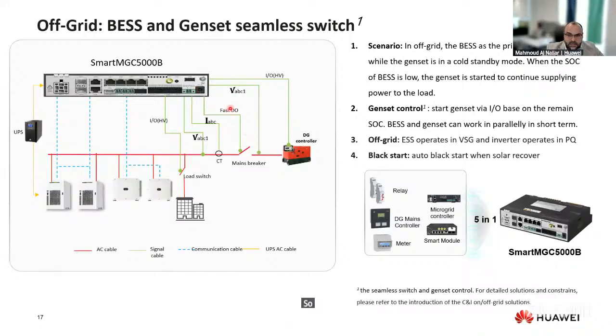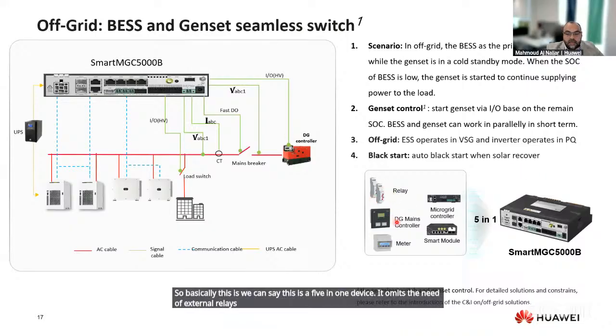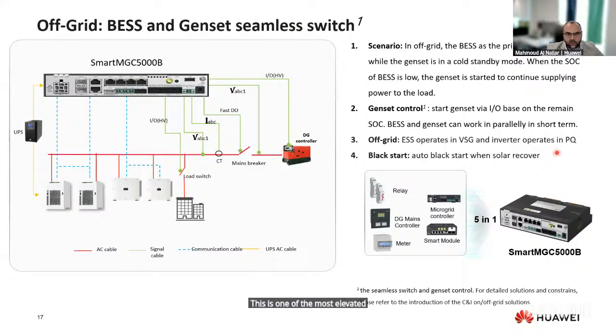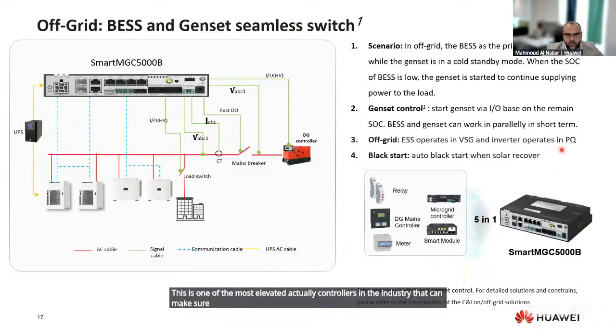So basically, we can say this is a 5-in-1 device. It omits the need of external relays, a DG main controller, an external meter, and it has module expansion with multiple slots, and a microgrid controller. This is one of the most innovative controllers in the industry that can make sure the system can operate smoothly and is minimal and easy to set up.